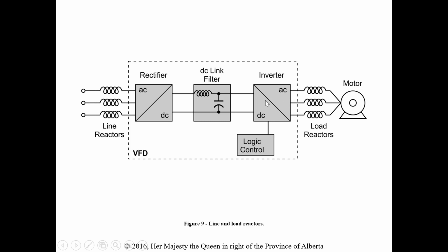But as we talked about in UPS with the pulse width modulation, we can determine the frequency because we're basically creating our own sine wave on the output of that inverter. So we can manipulate the frequency, and that's how we can change the supply to the motor. This logic control, again, could be a computer, a PLC, feedback from the motor, could be all kinds of things to basically change that. Okay, it could be you sitting right in front of the VFD and manipulating it on the control panel as well.